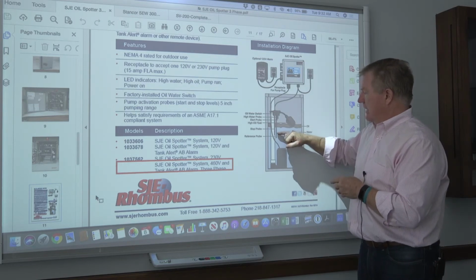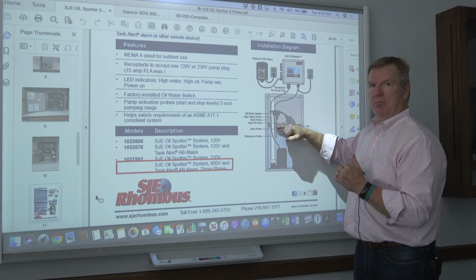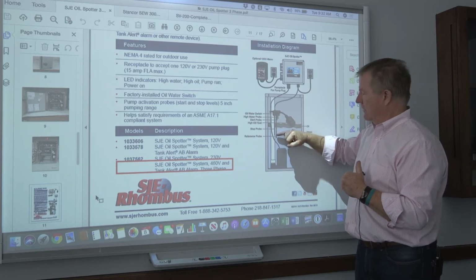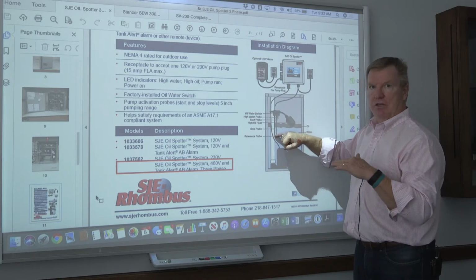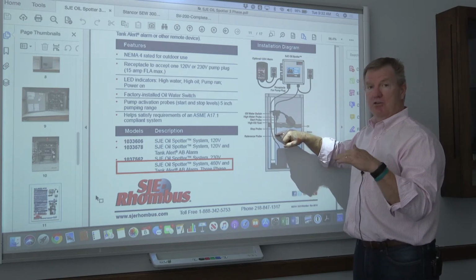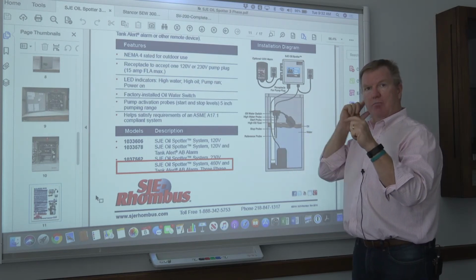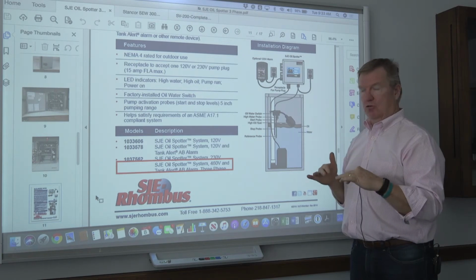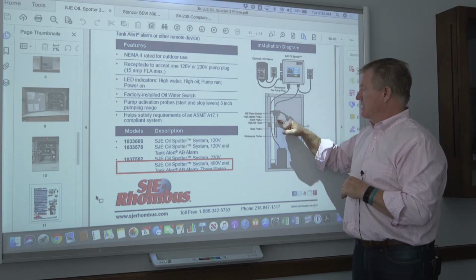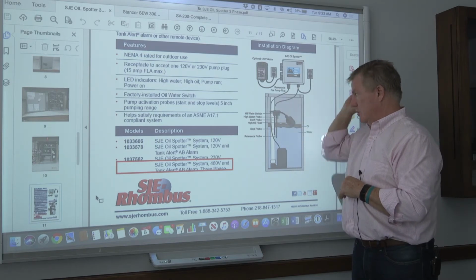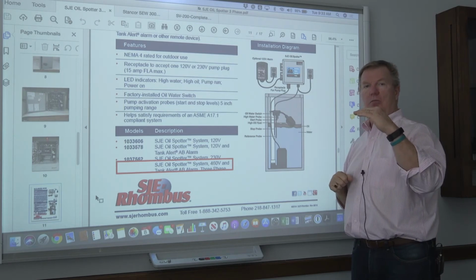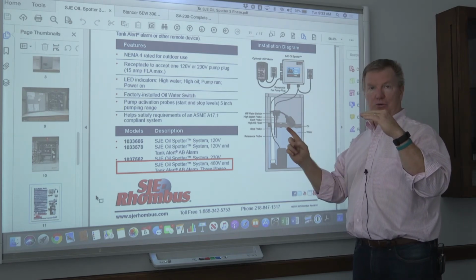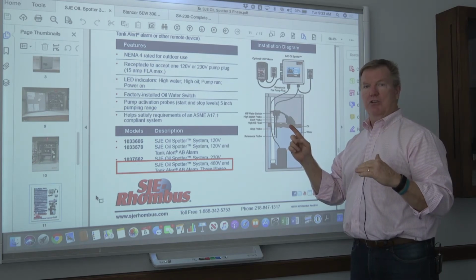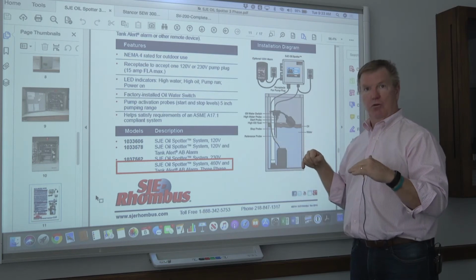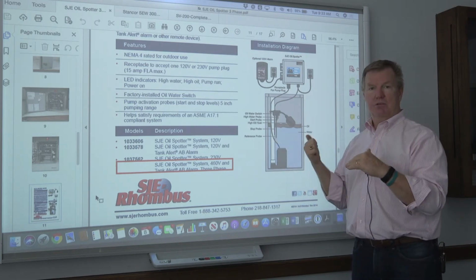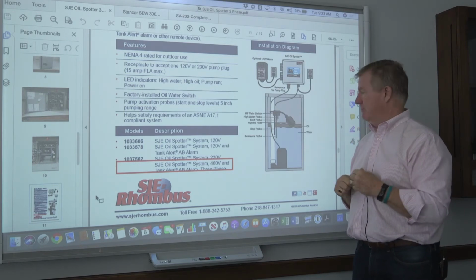The next one up is the stop level. So that tells the sump pump the level at which to stop. So whatever level the bottom of the stop probe is, that's where the off level will be for the sump pump. So as soon as the water breaks from the bottom, so that probe is no longer inside the water, that's when the pump turns off. The next one up is the start probe. So when the water hits the start probe, it makes contact with that probe, the sump pump will turn on. It will pump it down until the water level reaches the stop probe level, and then will turn off. 99% of the time, that's where this sump system will operate, between the start and the stop probe.